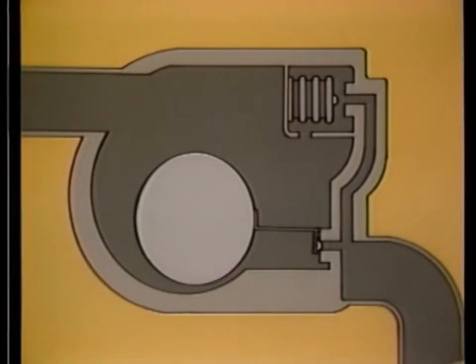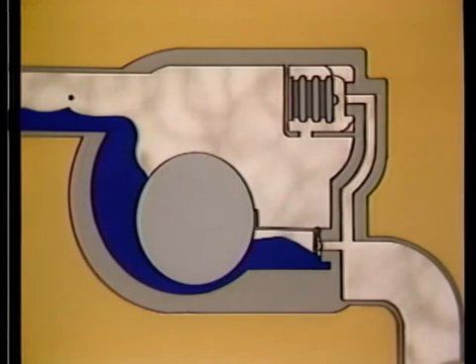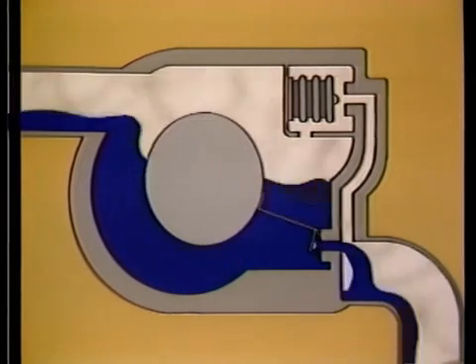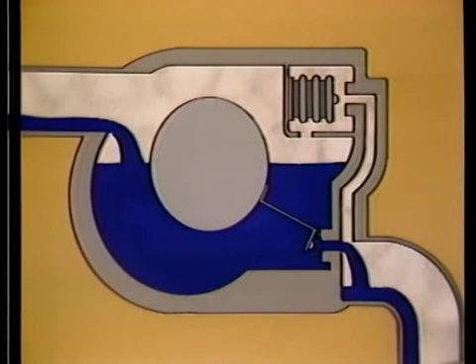At startup, the float is down, the float valve closed, and the thermostatic valve wide open. Non-condensible gases reaching the trap are immediately vented through the thermostatic valve at the top of the trap. Condensate collects at the bottom of the trap until the float begins to rise, opening the float valve. The float valve normally drains continuously from this point.